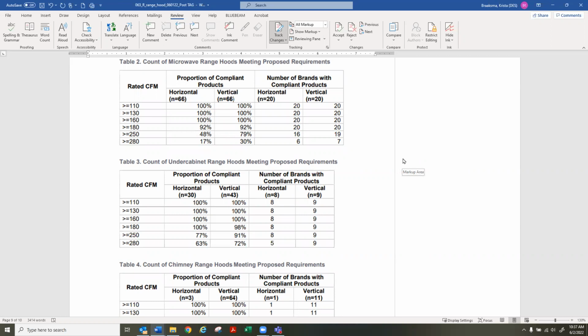And then also, to touch on some input that was brought up earlier about makeup air, what impacts this is going to have on makeup air, especially on smaller dwelling units. Just overall trying to identify what is the appropriate CFM. I think we have some organizations that are working on this with lab testing to prescribe a standard that works. From my position, I would like to see how that develops for the next code cycle before voting on something like this. And those are my comments.